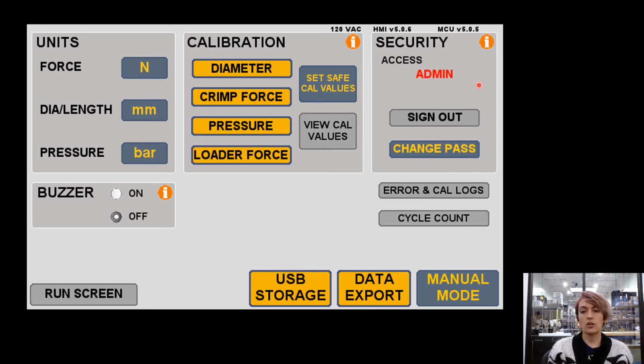Then we have the security box. In here is where you will switch user access modes. So you can be logged in as an admin, an operator, a calibration tech, or an engineer. And the various user access modes limit the availability of settings in the machine. So you can refer to your manual to see which settings are available under which user access mode.